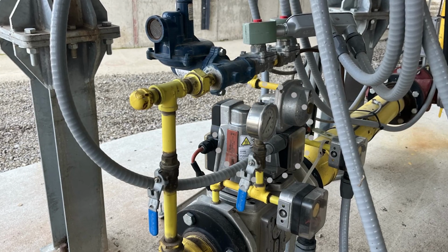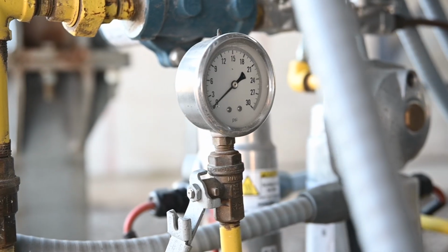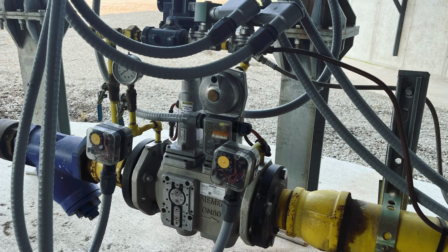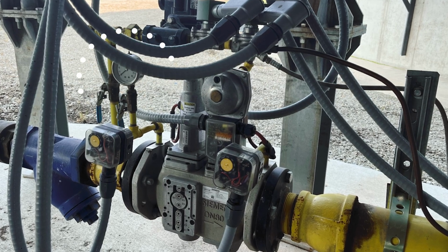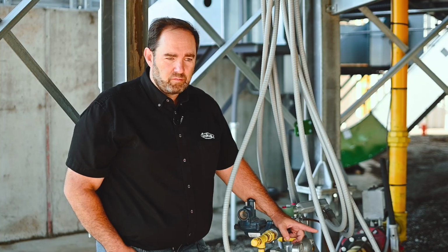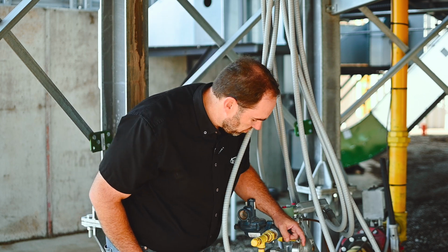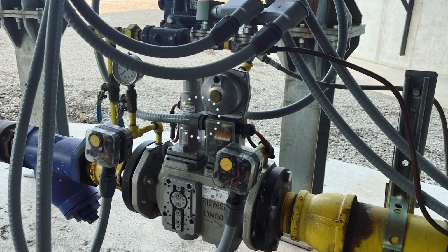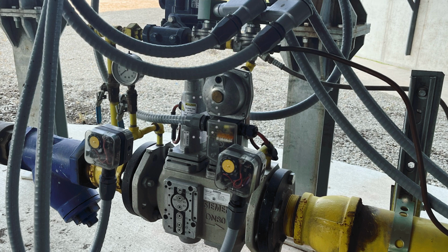There's also an incoming pressure gauge here. The gauge will read in PSI, or pounds per square inch. We want to see 6 to 9 PSI on this gauge of incoming fuel pressure, whether it's propane or natural gas, either one. Then there are two solenoid valves, or safety shutoff valves, in the valve block.